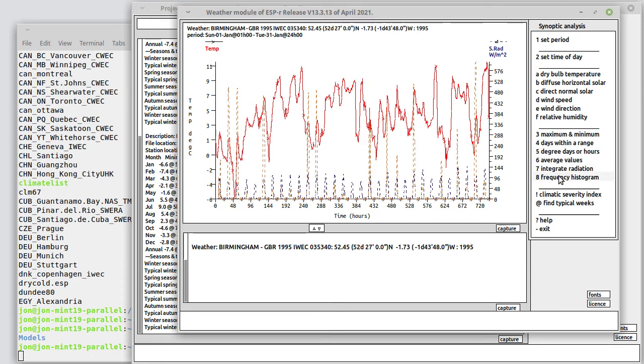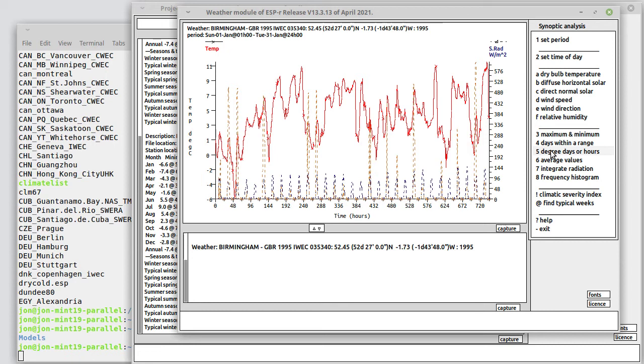Let's think in terms of these degree days or hours. This is a metric which dates back many decades. Essentially it sums up the difference for each hour over the period—how many degrees of difference between some base heating and cooling temperature and the ambient temperature outside. The bigger the magnitude of the degree day number that's reported, the more extreme the weather.